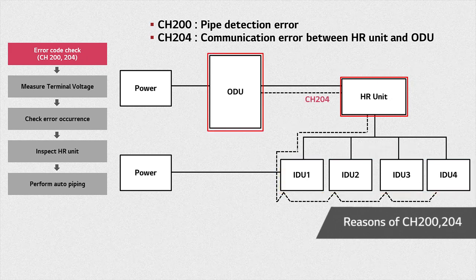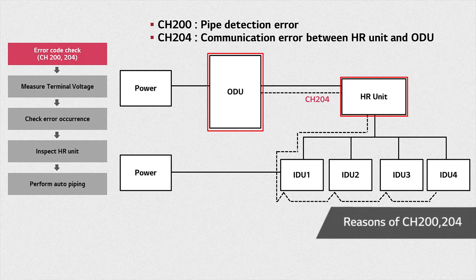On the other hand, error CH204 occurs when there is a communication error between the HR unit and the ODU. The causes for error CH204 include failure in the HR unit's communication cable and power cable, or a malfunction in the HR unit's PCB.